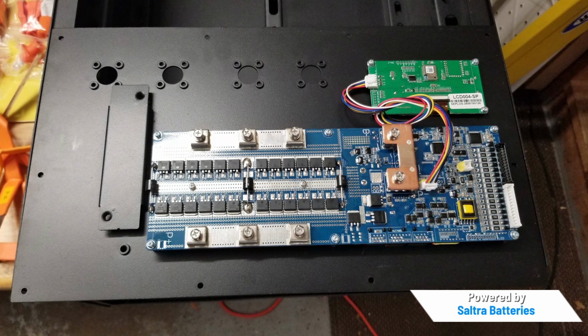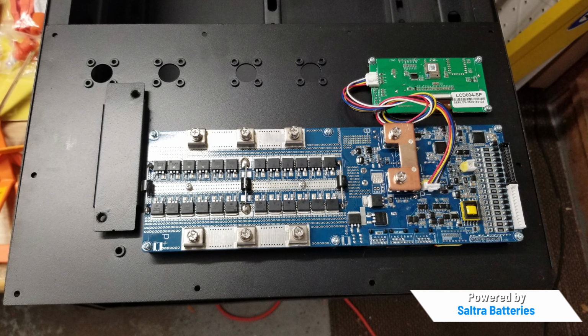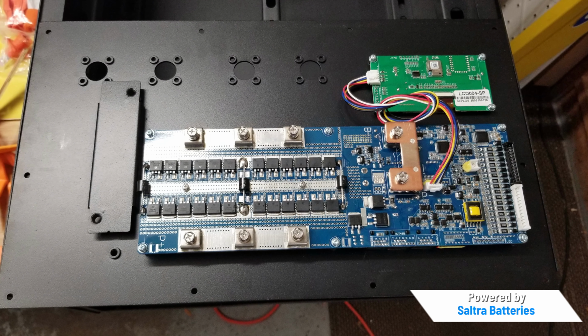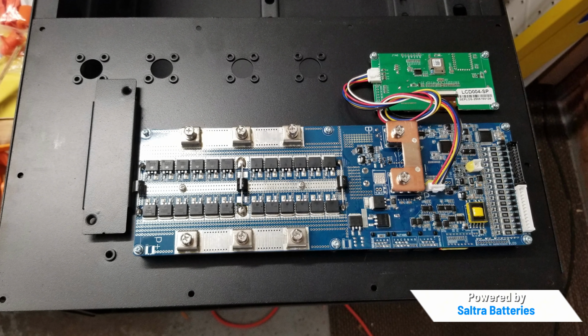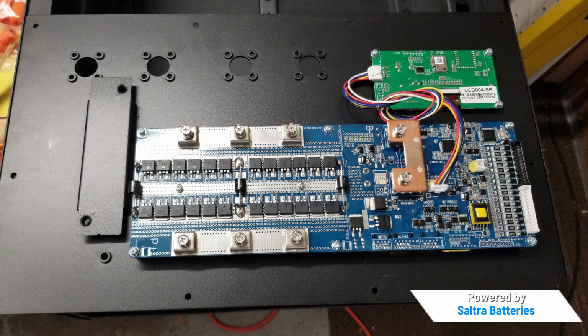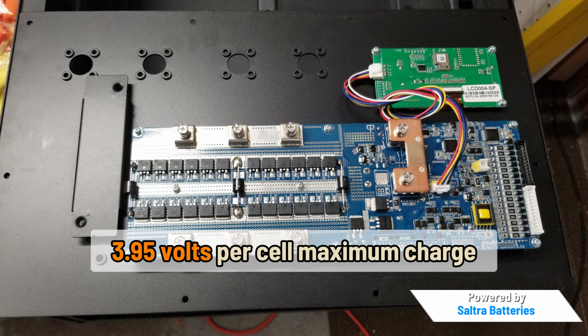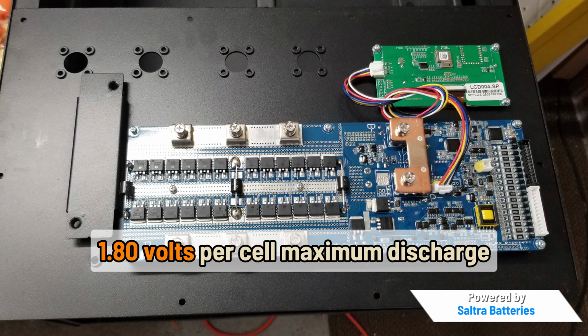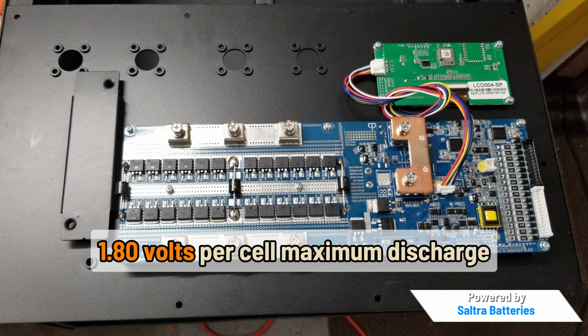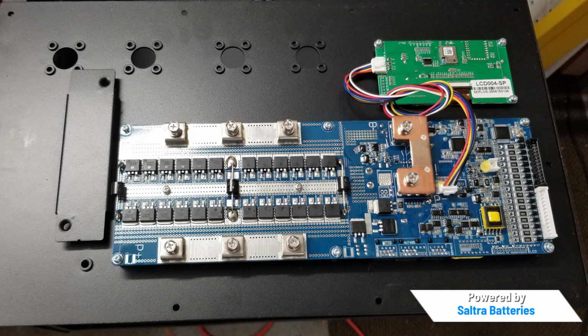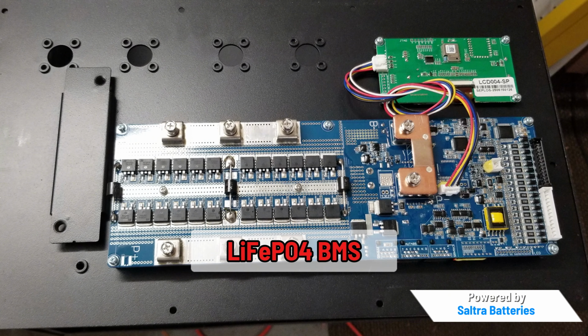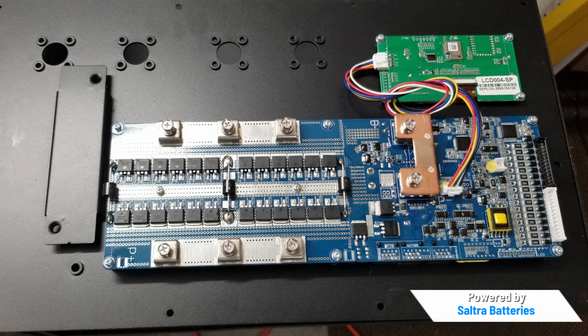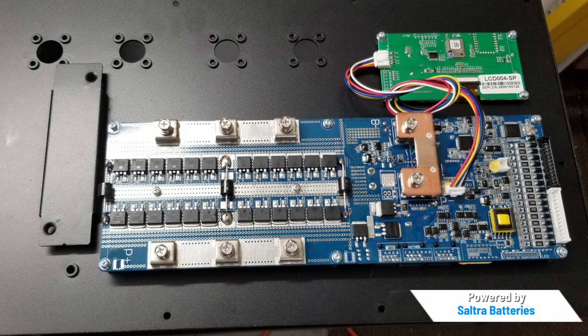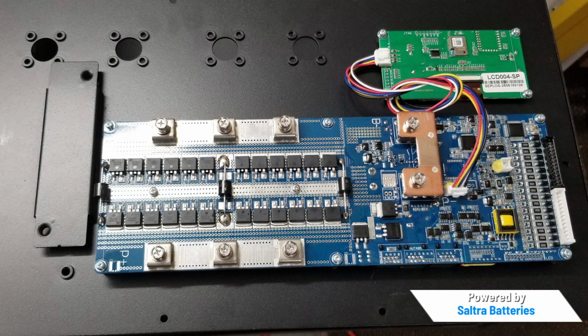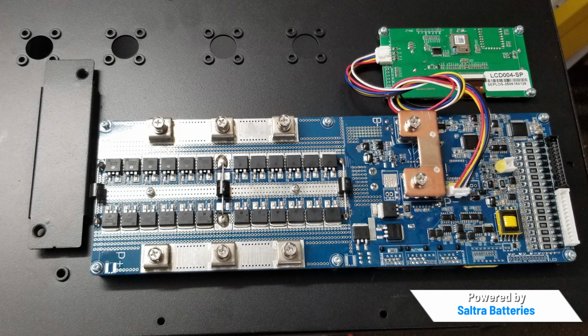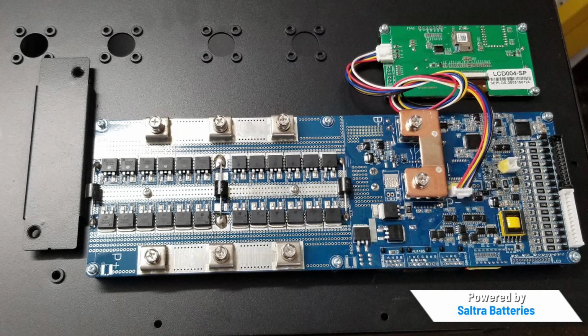This is the Seplos 200 amp Smart BMS. It was pre-configured for NaFP sodium-ion chemistry before this build started. The voltage parameters are already set. 3.95 volts per cell maximum charge, 1.80 volts per cell minimum discharge. Those numbers matter. This is not a LiFePO4 BMS. If you used LiFePO4 settings on a sodium-ion pack, the cutoff voltages would be wrong, and you'd either undercharge or over-discharge the cells. Chemistry-specific configuration is mandatory.